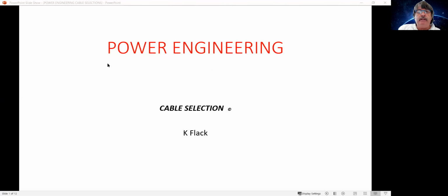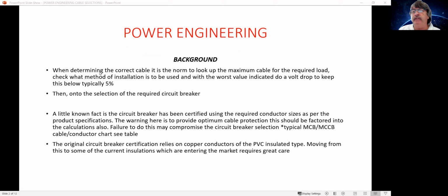So today, power engineering conundrum is about the cable selection. So let's have a look at a number of things and let's have a look at the background to this. When we normally determine what correct cable we're going to use, we look traditionally at the load, we check the method of installation to be used, and with the worst value indicator, do a volt drop to keep this typically below 5%. And then we go on to the selection of the required circuit breaker.